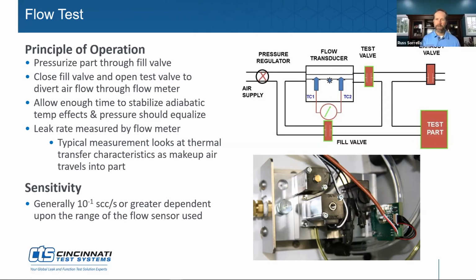Yeah, so I always articulate that as we measure the amount of flow that it takes to maintain pressure in the part. So same thing you said. I just wanted to say that. Yes, absolutely. With leak testing, it's said a couple of ways differently, so that it makes sense to everyone.